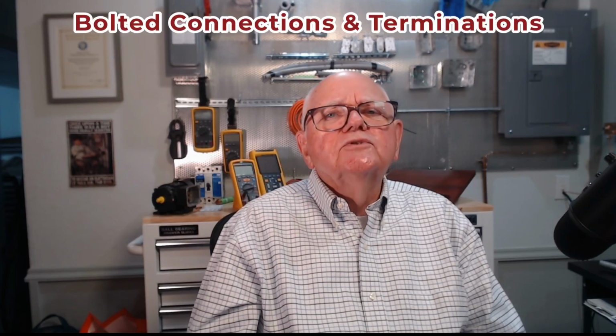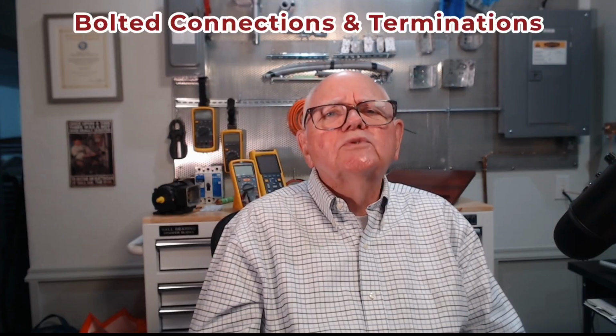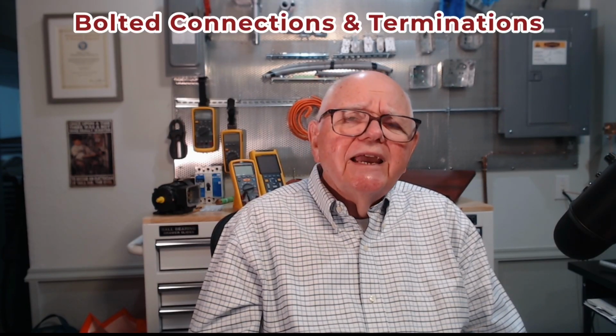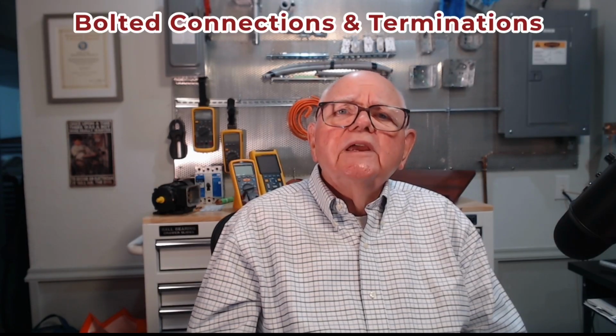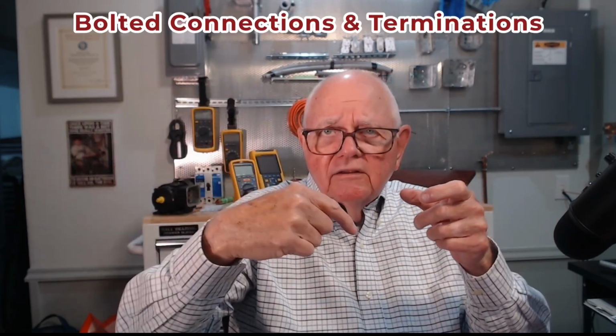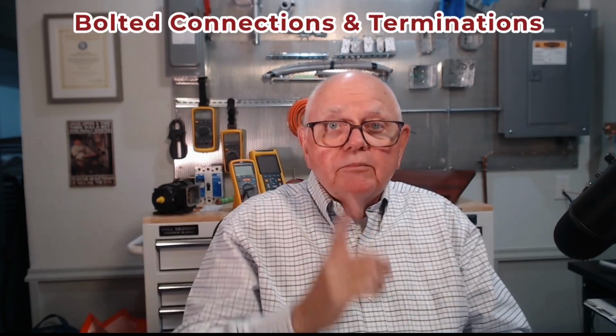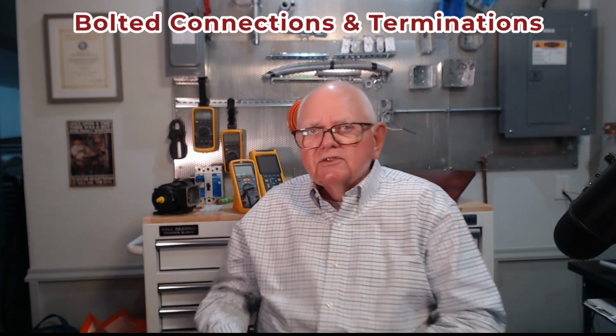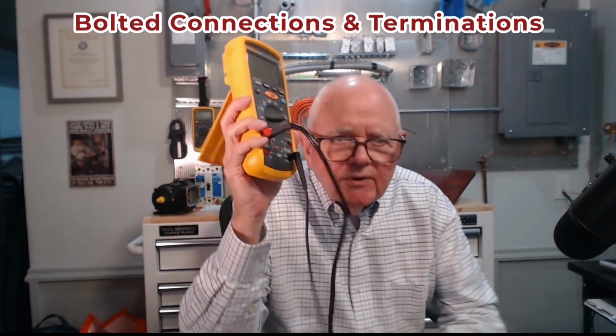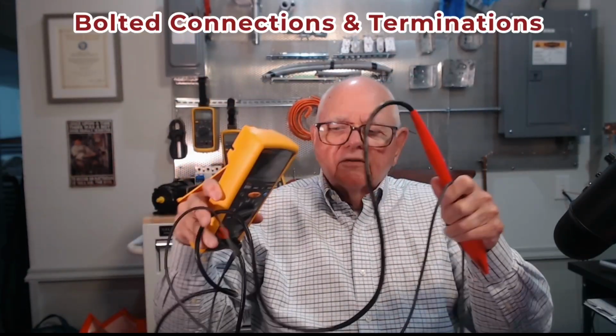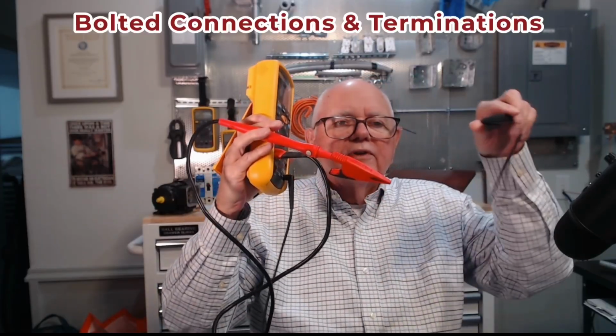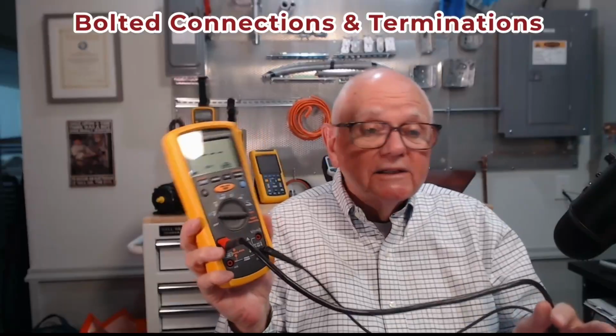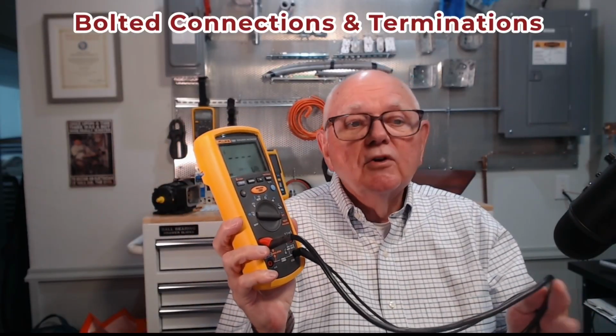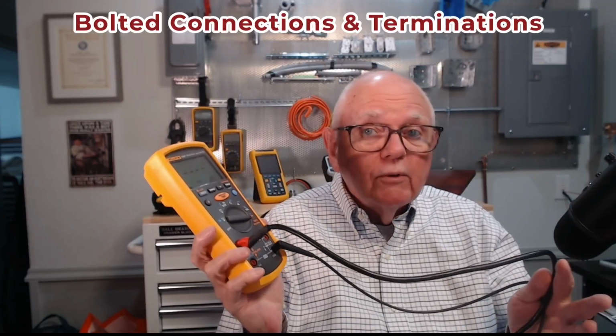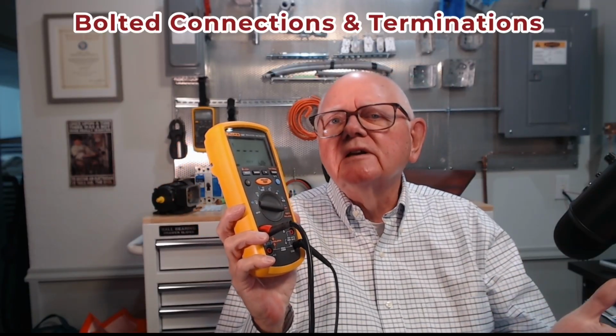Or one other thing that I can do is, and I don't really do this on panel boards, but you'll see it more in switchgear. We can go ahead and shut it down and measure the resistance between the bolt head and, say, the bus bar. So if I measure the resistance between the bolt head and the bus bar, I get a value. If I use something, let's say, like the typical mega-ohm meter, I'm going to get a certain value, right? And so I take one test lead and I'll put it on the bolt head. I'll put the other test lead on the bus bar. On an insulation resistance tester like this, the lowest value of resistance we might expect to read would be maybe 0.1 ohms. And that's as low as it can possibly read, 1/10 of an ohm.